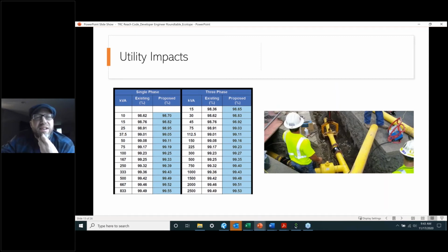The first piece is utility impacts, and Brian mentioned some of the decisions made for his project. A couple of key points: what we've seen for costs of gas connections to buildings can range from 20 to 45,000 dollars - that's the price to get the gas from the street to the boiler. Those costs have to be factored in when doing comparisons. The other piece to factor in are the venting costs. In California, a lot of the plants are on the roof, so the venting is pretty minimal.